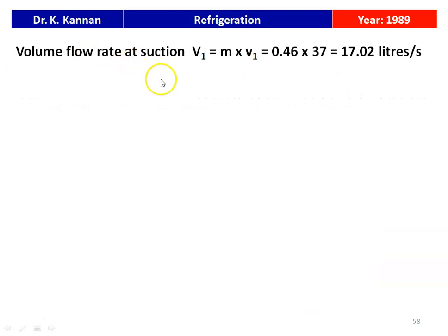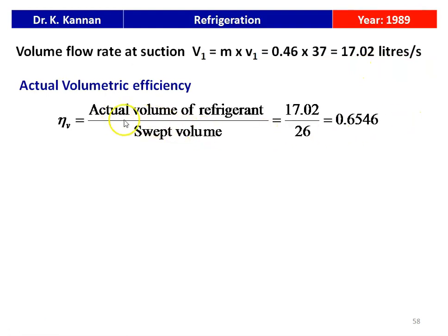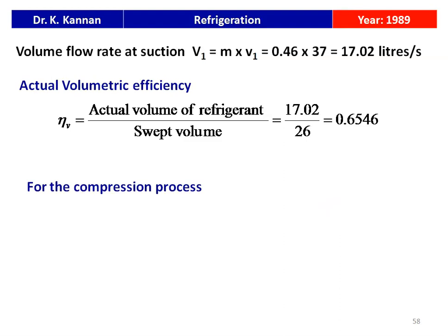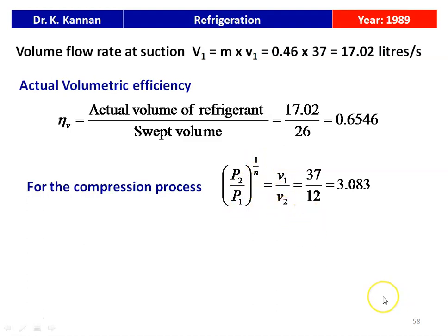Given data: clearance ratio C = 0.04, swept volume = 26 liters/s, mass flow rate = 0.46 kg/s, specific volume at suction V1 = 37 liters/kg, specific volume at discharge V2 = 12 liters/kg. The volume flow rate of the refrigerant = mass × specific volume = 0.46 × 37 = 17.02 liters/s. The actual volumetric efficiency = actual volume / swept volume = 17.02 / 26 = 0.6546, i.e., 65.46%.